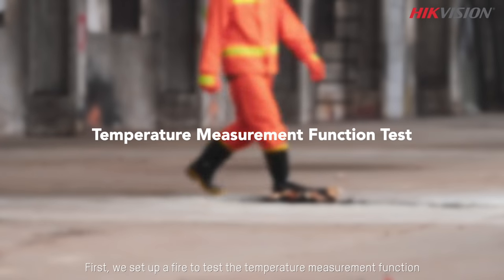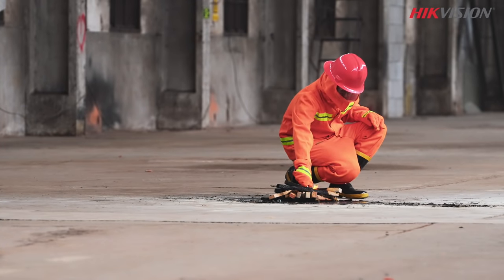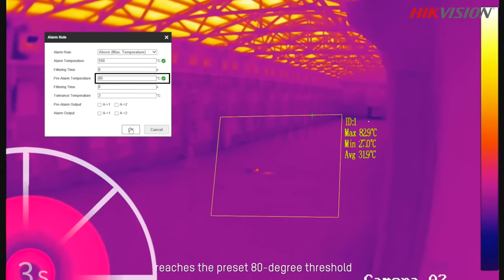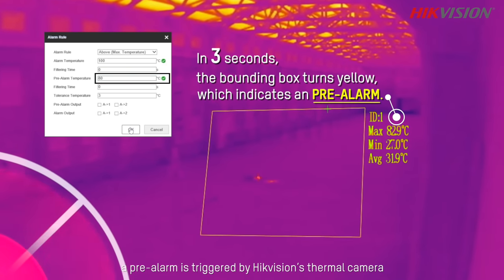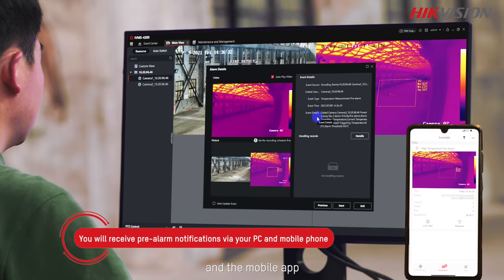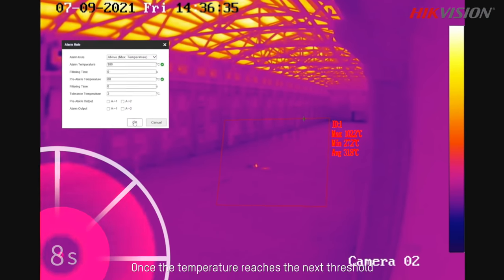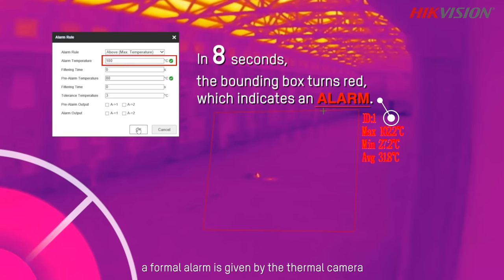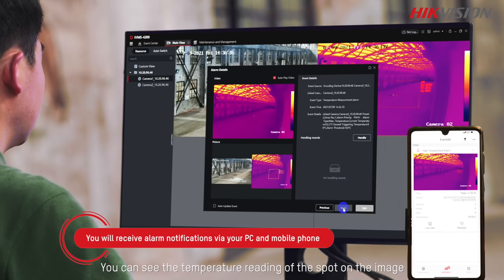First, we set up a fire to test the temperature measurement function. As soon as the detected temperature reaches the preset 80-degree threshold, a pre-alarm is triggered by the Hikvision thermal camera. A real-time image of the spot is pushed to PC client and the mobile app. Once the temperature reaches the next threshold of 100 degrees, a formal alarm is given by the thermal camera. You can see the temperature reading of the spot on the image.